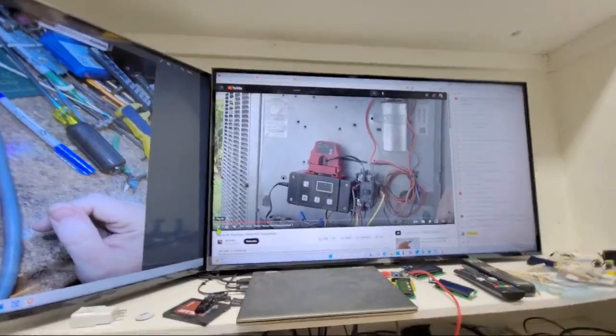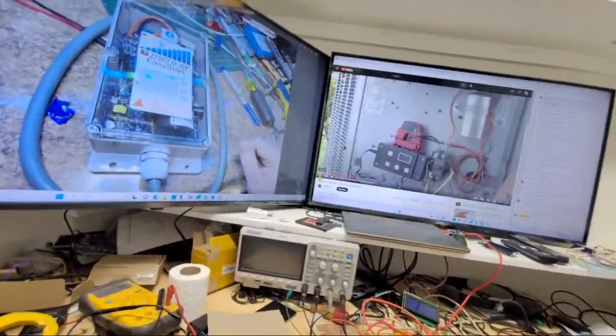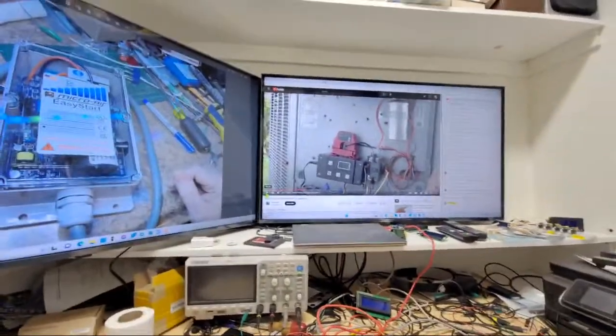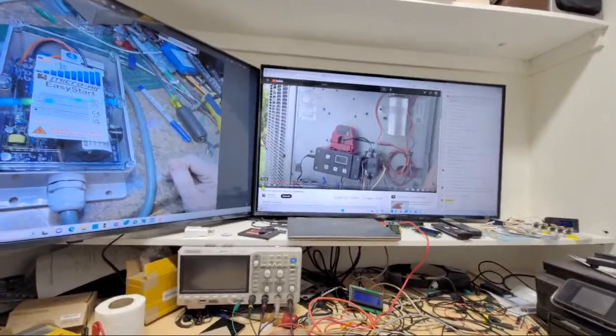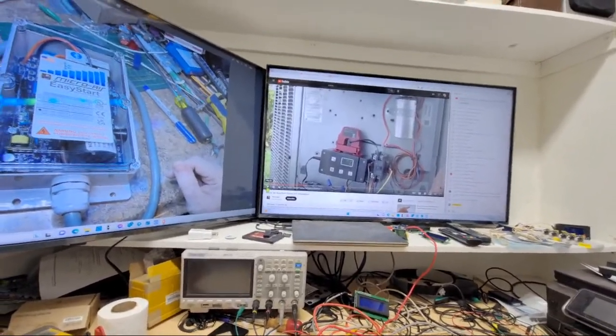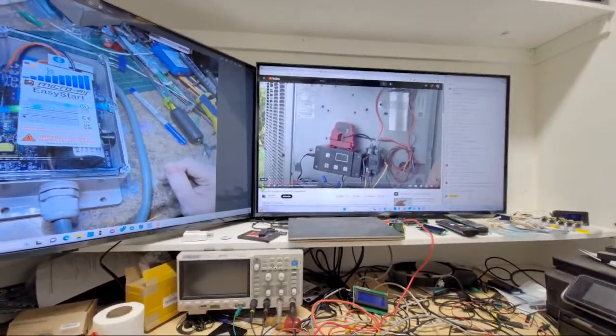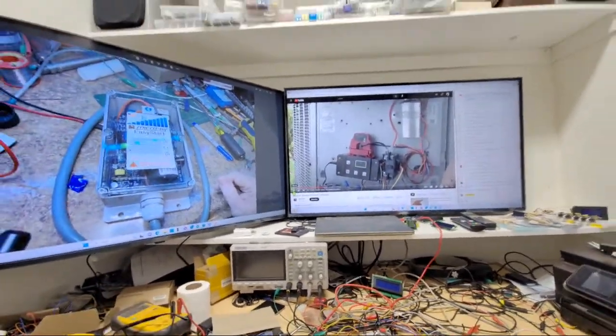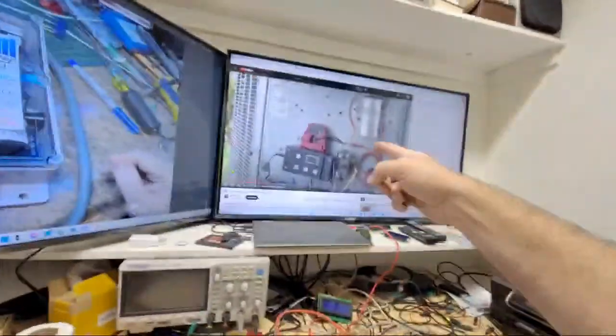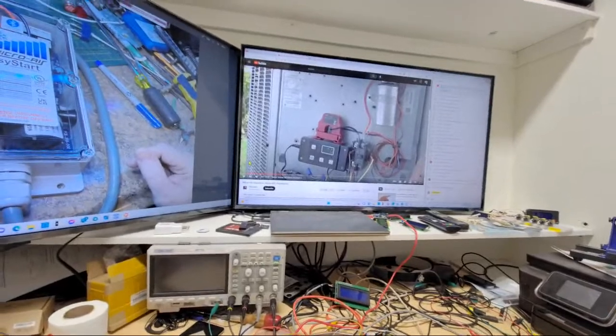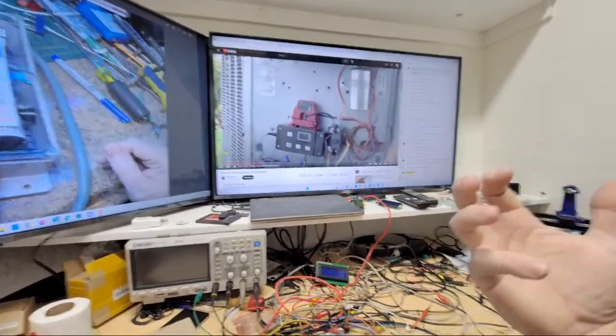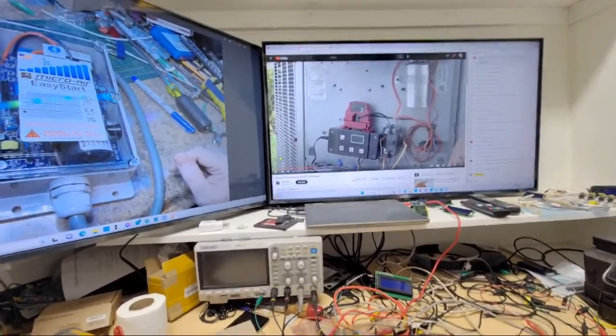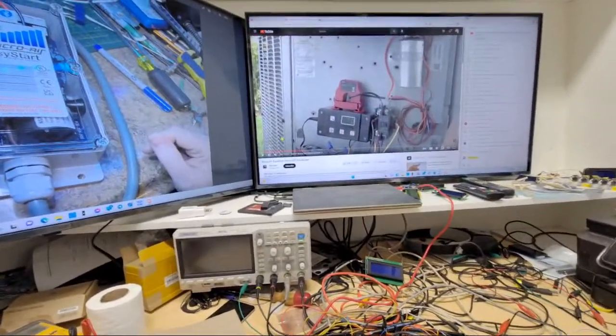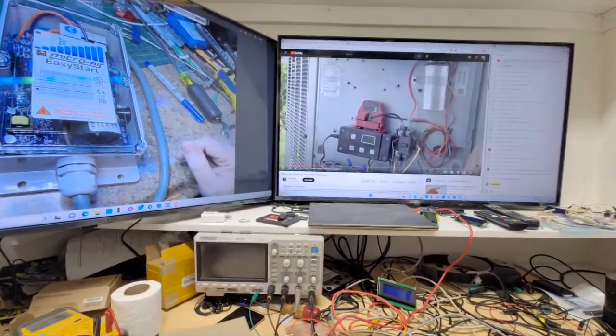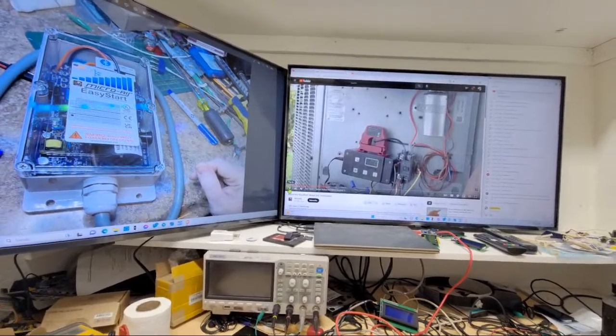Now I'll tell you, he's not going to get all the inrush current. The inrush current, like I had drawn up here, is going to be your locked rotor amps, and if it's a 5-ton scroll, for example, it's probably 160 amps at the first instant you throw that power. But then it drops quick, especially if you had a start component, but even without it, it's still a fraction of a second, and then it drops down to run load amps within a second or so without the hard start. And your meters are not fast enough, and even that one's not fast enough to capture it, but you probably can repeat it and get some sort of value, which this guy's going to get. And I've done the same exact thing that this guy's doing, a before and after comparison. So it is a comparison. It's not the real inrush amps. But it is a value to compare.